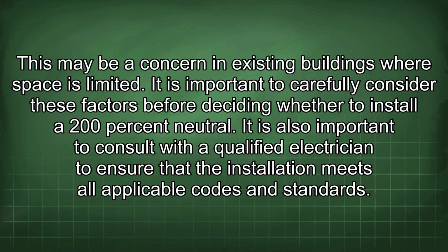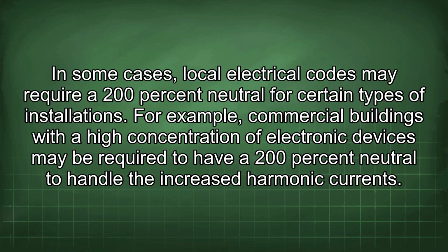It is also important to consult with a qualified electrician to ensure that the installation meets all applicable codes and standards. In some cases, local electrical codes may require 200% neutral for certain types of installations. For example, commercial buildings with a high concentration of electronic devices may be required to have a 200% neutral to handle the increased harmonic currents.